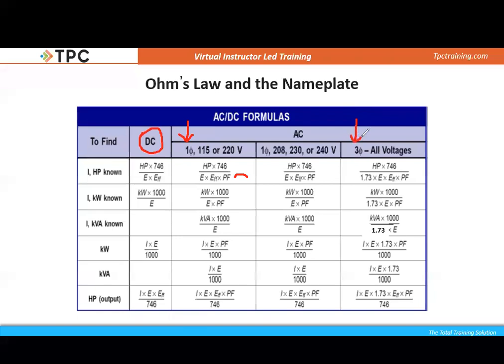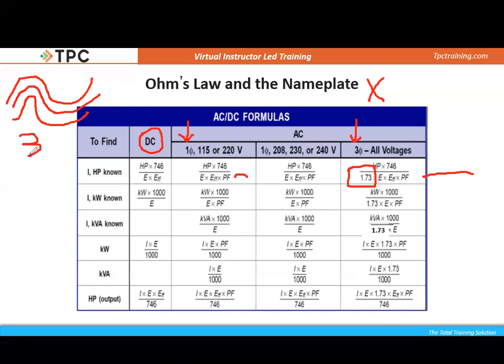The minute that we get into three phase, I still have to look at what power factor is, but I have to include 1.73. And why do I have to include 1.73? Because remember our three phases. Our three phases are not embedded right on top of each other. In other words, they do not all reach the peak at the same time. If they did, we could get rid of the 1.73 and just put 3 in there.